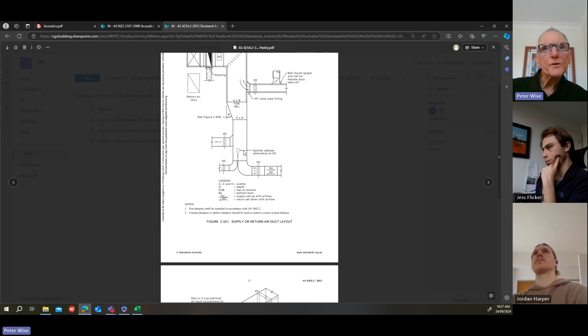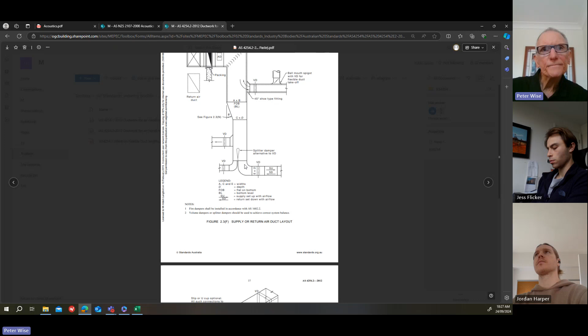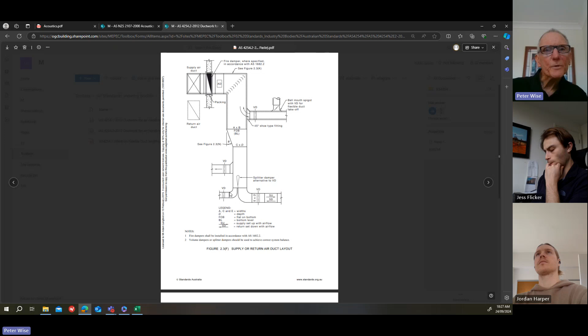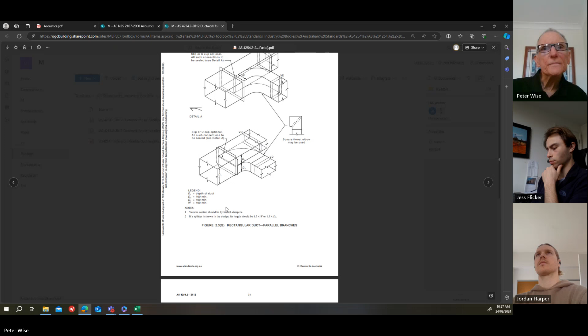But to be honest, they're not used that much anymore, because there's a rod that sticks out through the duct, and over time with the air flowing over it, you get a bit of a rattle up. They can be a bit noisy because they start to rattle, and the connections can break. And if the connections break, then the damper is going to go one way or the other and block off the flow through one side. So generally, I wouldn't recommend using those. Even though it shows it here, you probably won't see them. But different manufacturers do things in different ways. So these are just things to help you if you need some help, I guess.